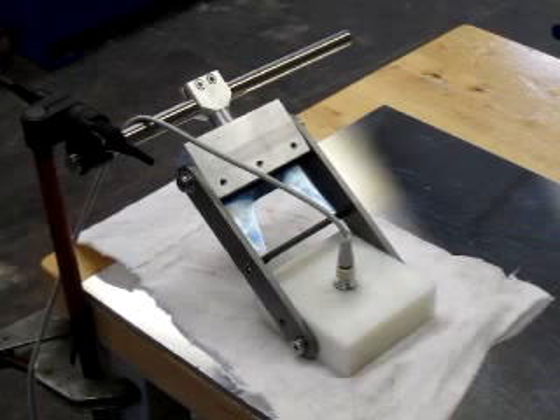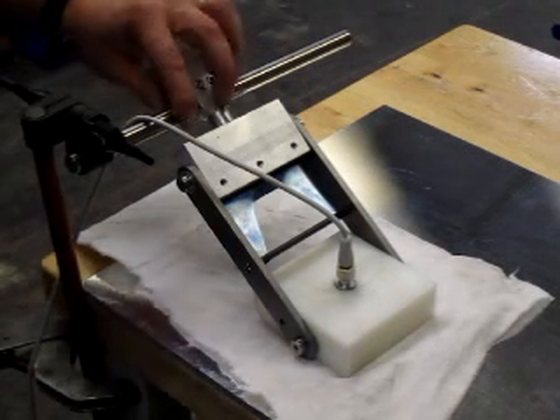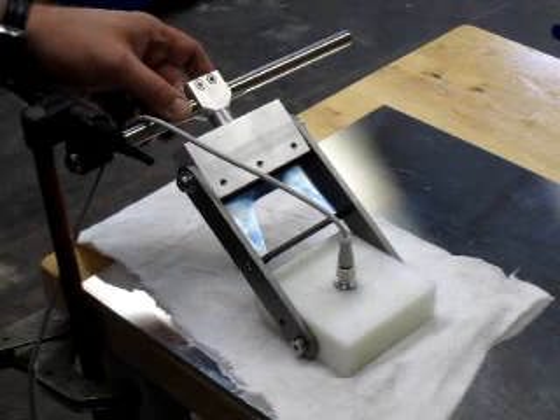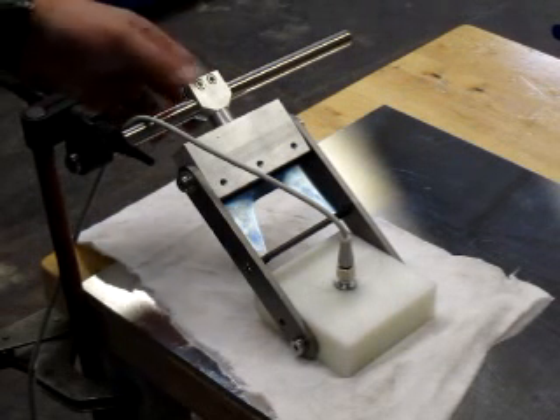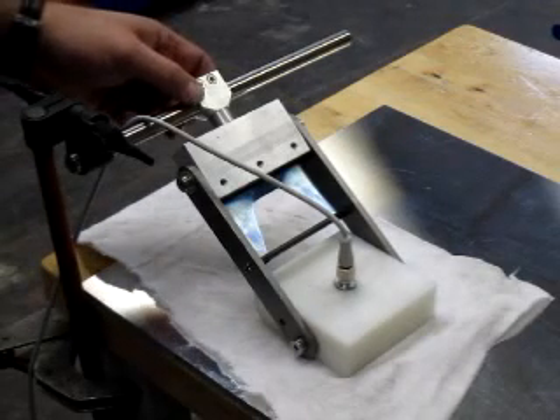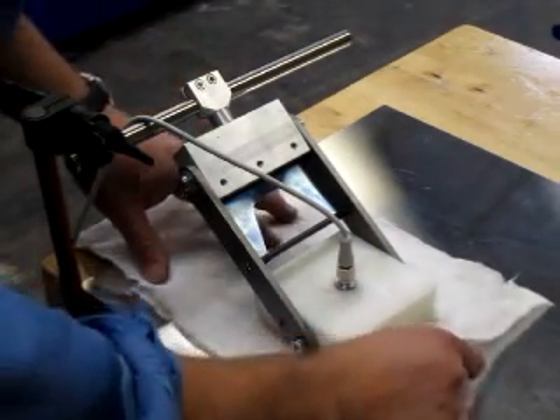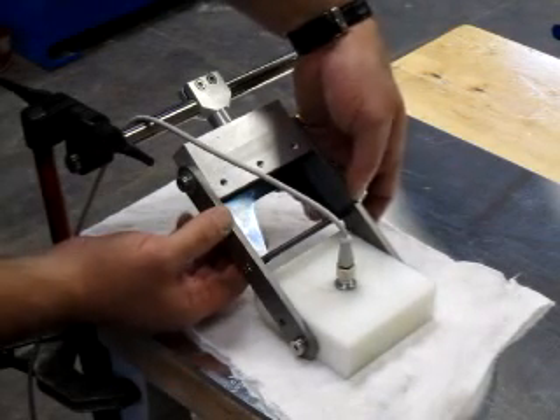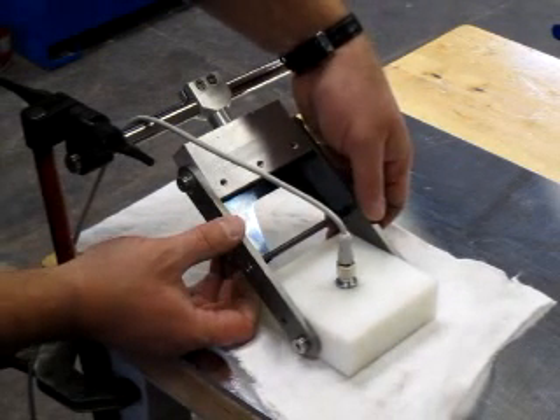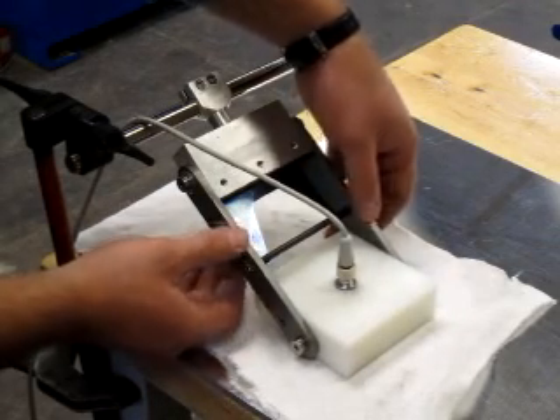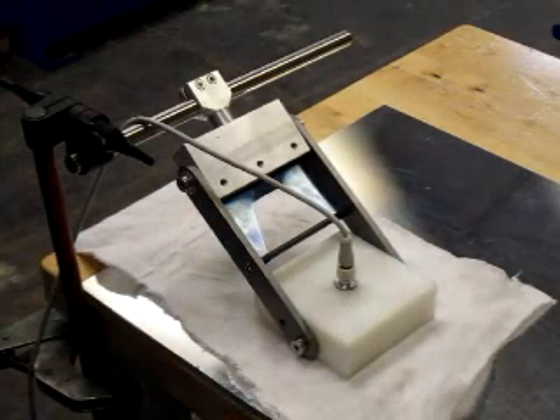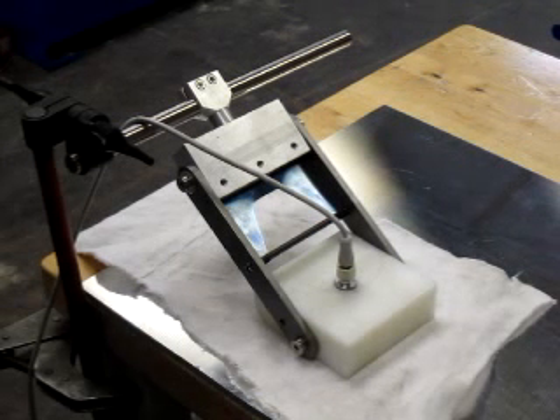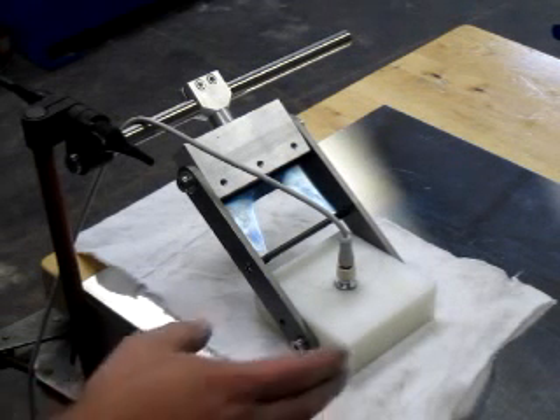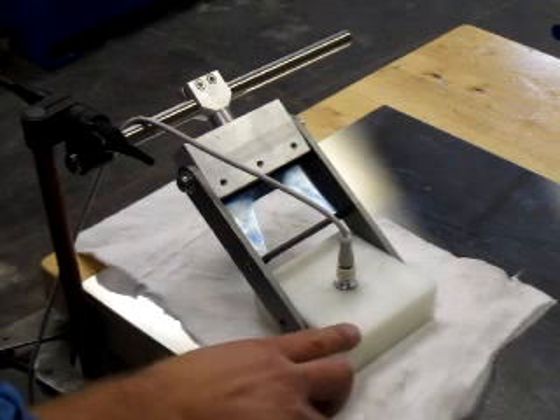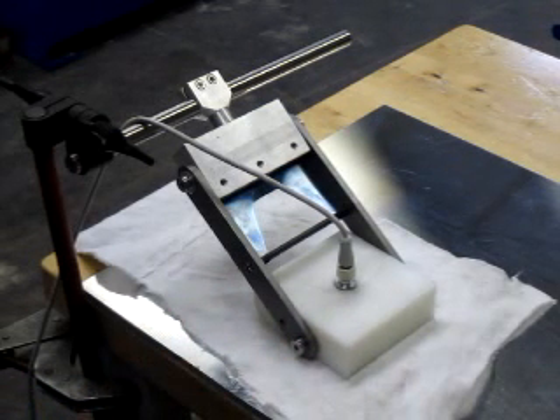We'll go through a couple of items to set this up. This arrangement right here is exactly the same as the encoders that are on the machine right now. So you'll have to mount some 5/8 rod someplace on the machine so that you end up with this arrangement here. There's a spring. This flat piece of steel here is actually a spring that's keeping downward pressure on this shoe, and I really don't know how much it's going to take. Obviously, the least amount of pressure that you can get by with is the best to prevent excess wear. I don't know if heat will build up on this or not. I guess we'll find out once we get the thing running.